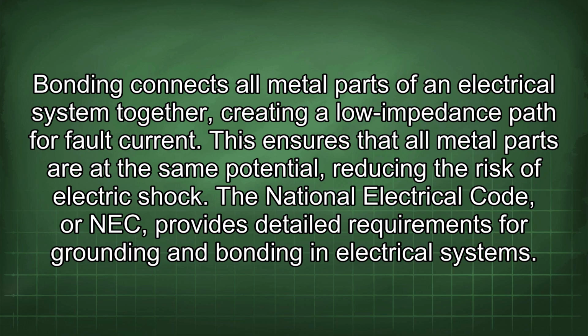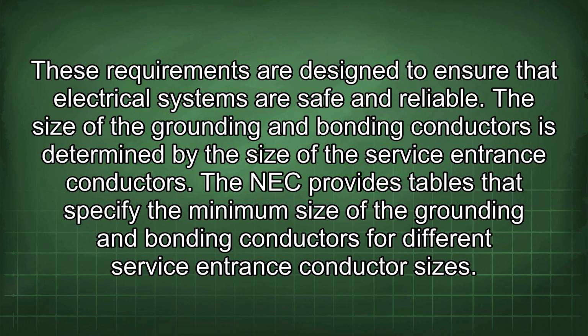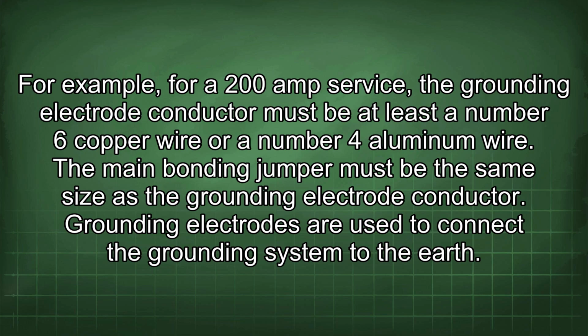The National Electrical Code, or NEC, provides detailed requirements for grounding and bonding in electrical systems. These requirements are designed to ensure that electrical systems are safe and reliable. The size of the grounding and bonding conductors is determined by the size of the service entrance conductors. The NEC provides tables that specify the minimum size of the grounding and bonding conductors for different service entrance conductor sizes. For example, for a 200 amp service, the grounding electrode conductor must be at least a number 6 copper wire or a number 4 aluminum wire. The main bonding jumper must be the same size as the grounding electrode conductor.